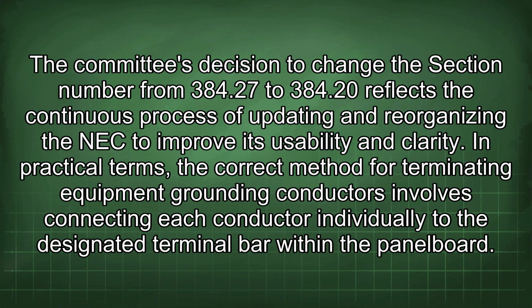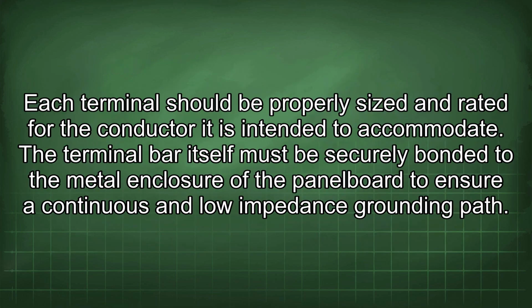In practical terms, the correct method for terminating equipment grounding conductors involves connecting each conductor individually to the designated terminal bar within the panel board. Each terminal should be properly sized and rated for the conductor it is intended to accommodate. The terminal bar itself must be securely bonded to the metal enclosure of the panel board to ensure a continuous and low impedance grounding path.